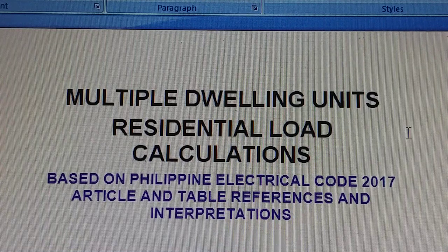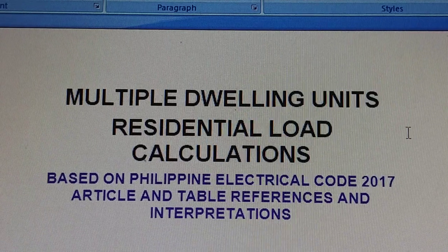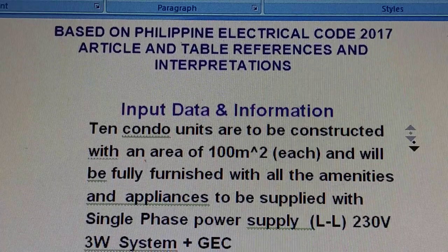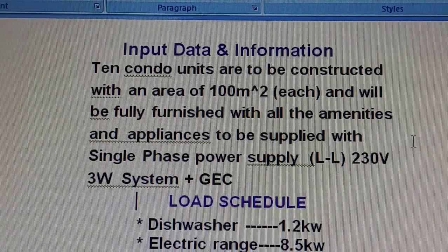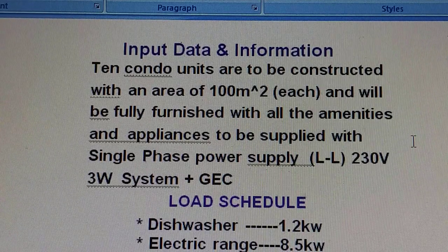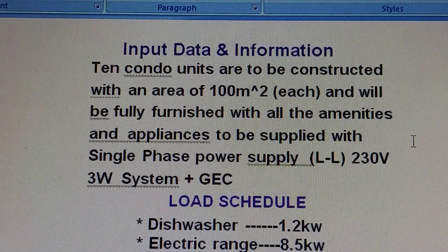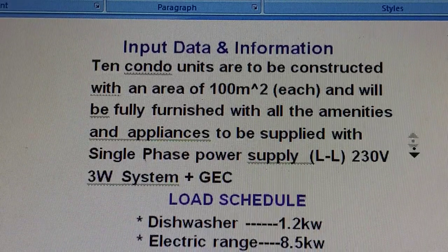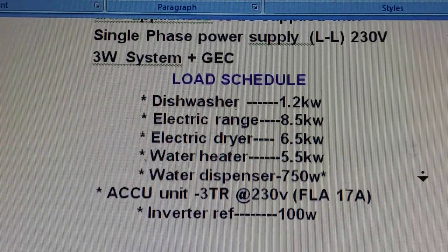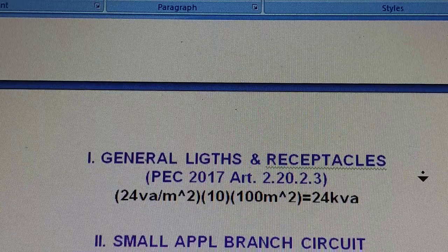Without further ado, let me start with my video presentation on calculation methods for multiple dwelling units. We have 10 condo units to be constructed with an area of 100 square meters each, fully furnished with all amenities and appliances, supplied with single-phase power supply by the line 230 three-wire system plus the GEC. We have here the load schedule for each condo unit.